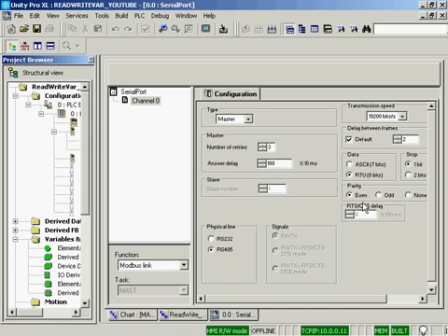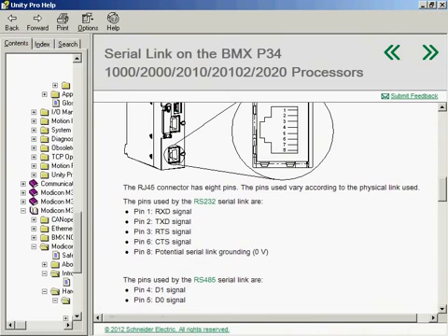The Modbus device that we're using is set to address 3, and all of the configuration parameters are set identically: 19.2K baud, RTU, 2-wire RS485, even parity, 1 stop bit. So let's look at the read VAR function block first.